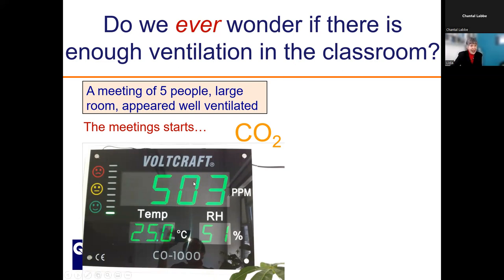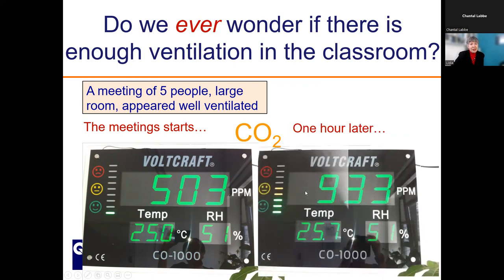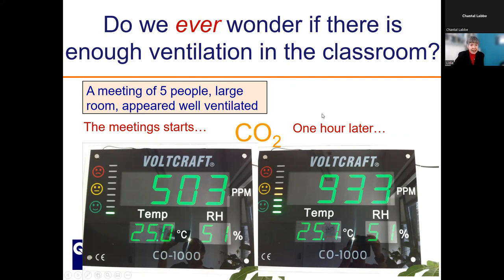Do we ever wonder if there is enough ventilation in the classroom or anywhere? This is a question I used to ask well before the pandemic, based on an example from a meeting in Germany at a research institute. The meeting involved five people in a large room that appeared well ventilated, with a big CO2 meter on the wall, visible from a distance. At the beginning the concentration was just over 500 parts per million with a smiley green face. One hour later it was not far from 1,000 — which would be red. My German colleagues told me these CO2 meters were already being used in German schools to alert students and staff to ventilation problems.